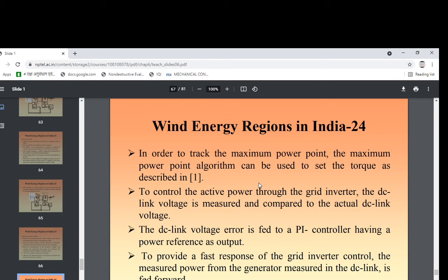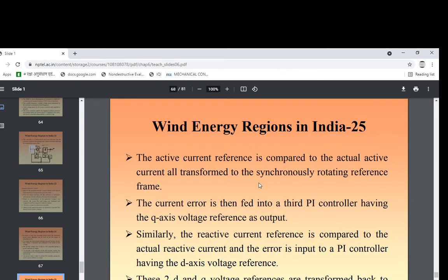To control the active power through the grid inverter, the DC link voltage is measured and compared to the actual DC link voltage. The DC link voltage error is fed to a PI controller, having a power reference as output. The active current reference is compared to the actual active current, all transformed to the synchronously rotating reference frame. The current error is then fed into a third PI controller having the Q-axis voltage reference. Similarly, the reactive current reference is compared to the actual reactive current, and the D and Q voltage references are transformed back to a stationary reference frame and the gate signals are calculated.